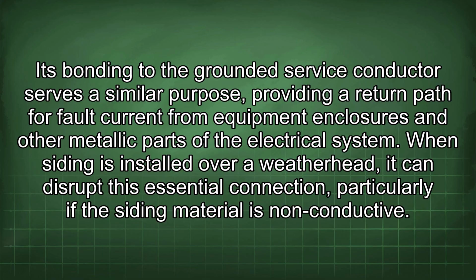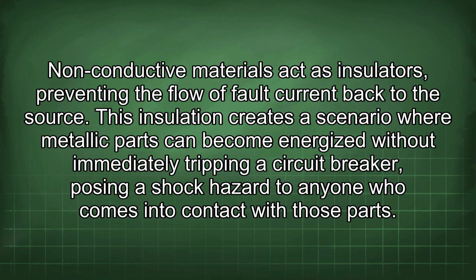When siding is installed over a weatherhead, it can disrupt this essential connection, particularly if the siding material is non-conductive. Non-conductive materials act as insulators, preventing the flow of fault current back to the source. This insulation creates a scenario where metallic parts can become energized without immediately tripping a circuit breaker, posing a shock hazard to anyone who comes into contact with those parts.